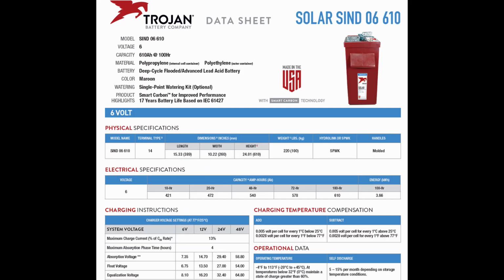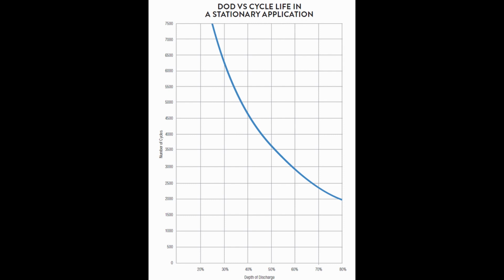So let's start with the flooded battery, and let's start with 30% depth of discharge per day, where we use 30% of our battery capacity every single day. Here on the data sheet, we see that it's rated for a 17-year life in partial state of charge applications, according to IEC 61427. 17 years, once per day, is 6,200 cycles. Looking at the cycle life chart, we see that 6,200 cycles can be achieved at that depth of discharge. We choose the lesser of the years or cycle life, assuming one per day, and here we see that this battery will last 17 years in that application if maintained properly.